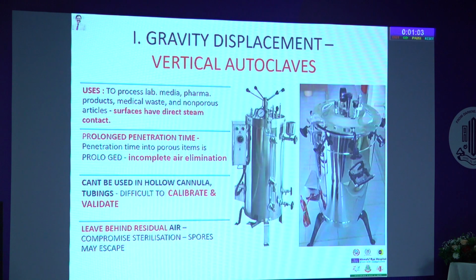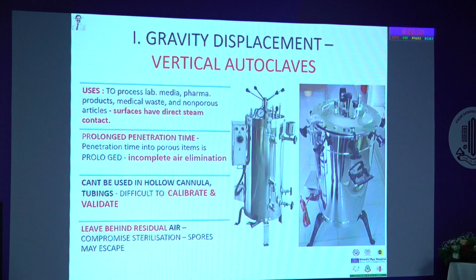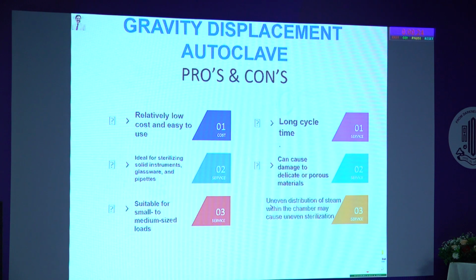It also takes prolonged time, so it's not really energy efficient, and there is incomplete air elimination. There are certain pockets, particularly the lower area, since it is gravity displacement, the lower bin may not be sterilized properly, and it can't be used for hollow cannulas or tubings because the steam doesn't reach those hollow cannulas and long tubings, and so it's also difficult to calibrate and validate the entire system. It also leaves behind residual air. That means there is a risk of compromising the important process for which this is used, that is sterilization. So these are the pros and cons for people who are going to buy or looking at this option.